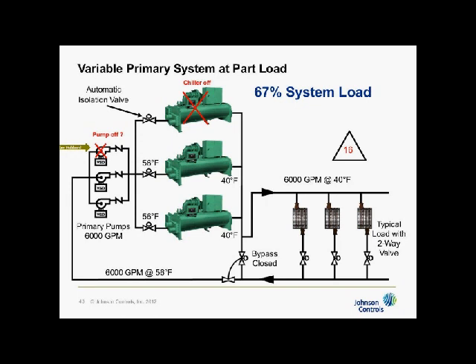Those are algorithms that something like a CPO would do. I've used the term CPO several times. That's chiller plant optimization for those who may not know. And that's what the third webinar will be all about. Anyway, I can choose here, but the point is that I can now turn this chiller off. So if I have 3 constant speed chillers that don't have CPO on all the auxiliaries and so on, now I don't have to run more chillers than I need. I can just overpump these 2 chillers when I have low delta T, which is now.